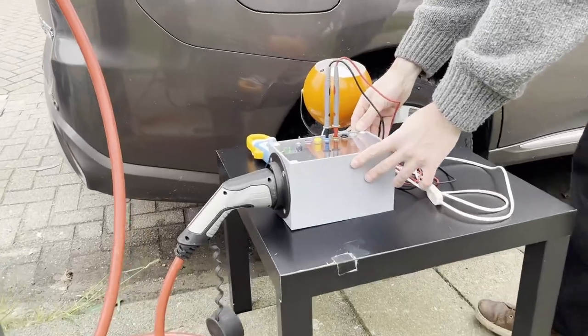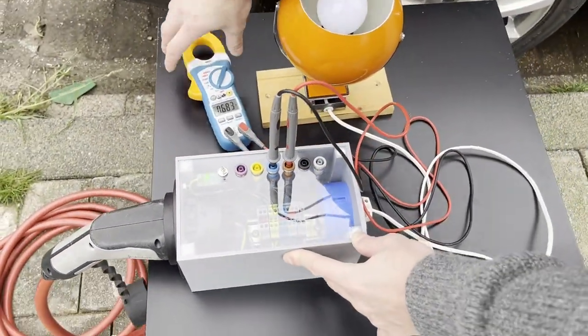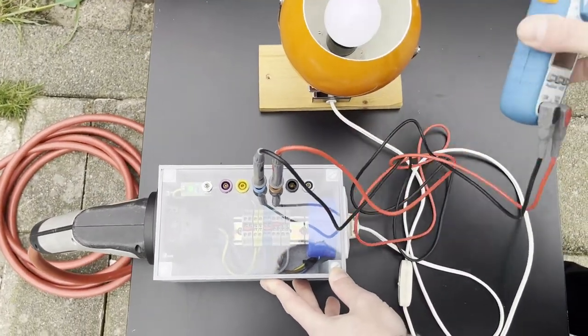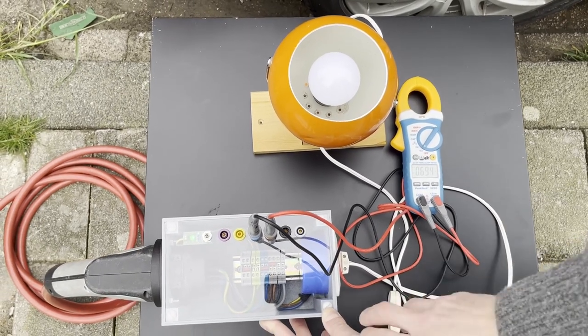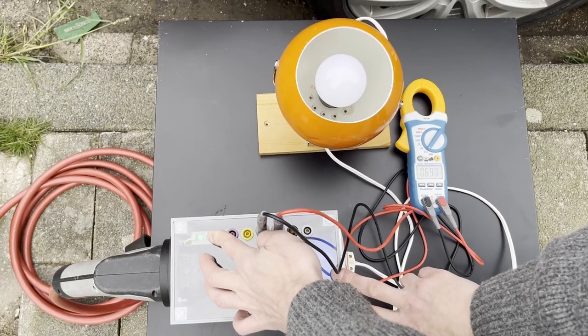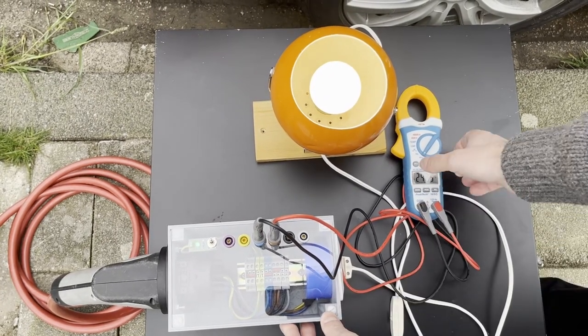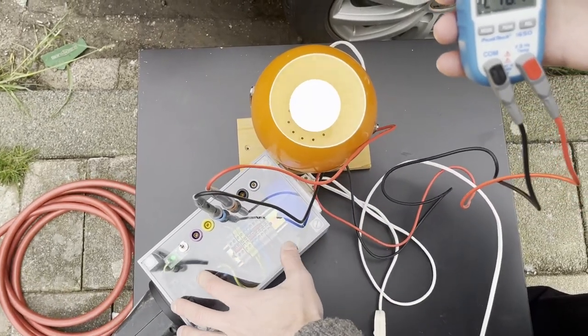And here's the most complete test setup in this video. As before, there is a control pilot circuit to simulate an electric vehicle and there is a socket outlet to power an appliance from the charging station. In addition, there are probes on the control pilot and power pins to be able to measure safely the operation of the charging station.